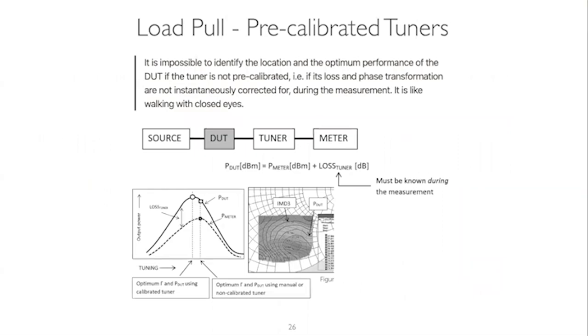So if you look at the bottom here, there's a power meter curve and a P_DUT, the device power. If you just look at the power meter curve, you'd say the right point is the right point. But in reality, if you de-embed the loss of the tuner, that point is totally different. So again, scalar load pull is used less and less - it's more for technology validation and things like that. But it's important to know that you really need to make sure you do a proper tuner calibration and de-embedding of the different S-parameter blocks to be able to do scalar measurements.